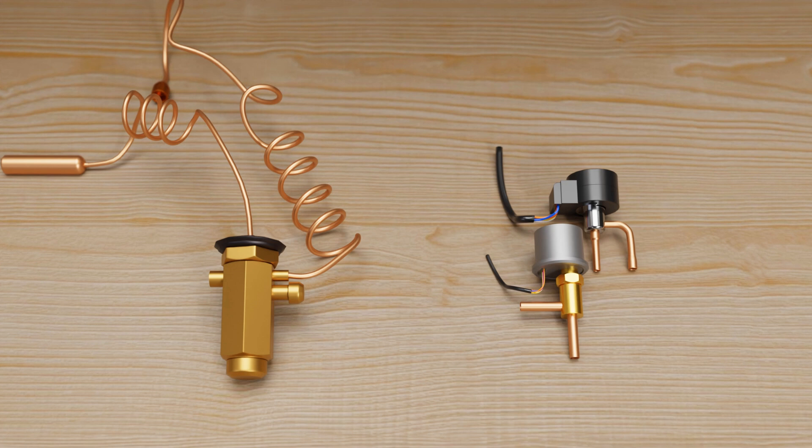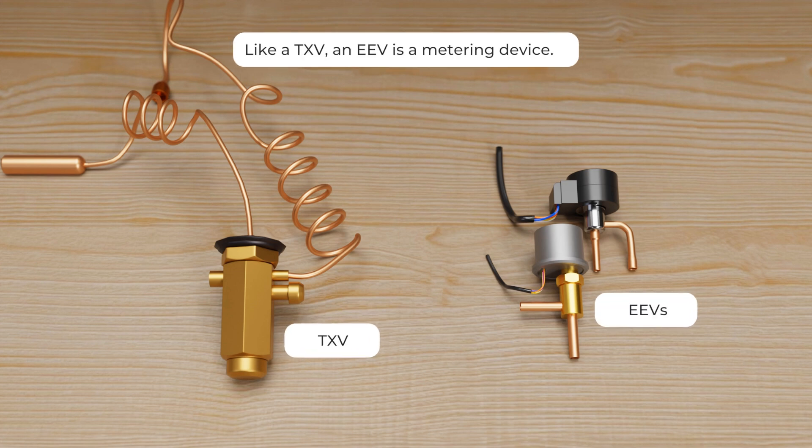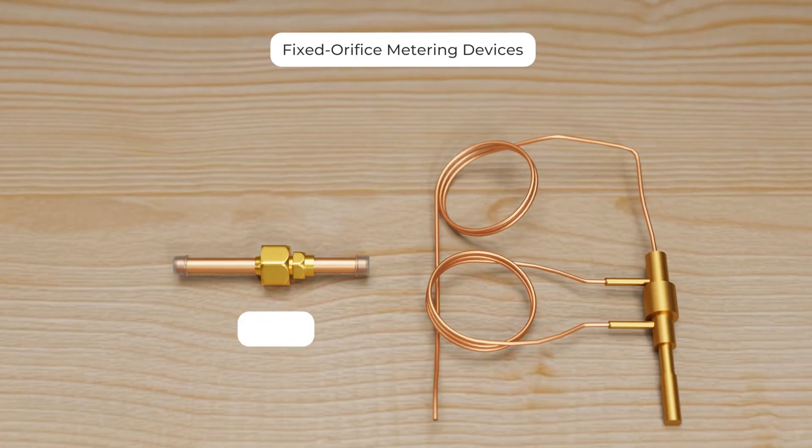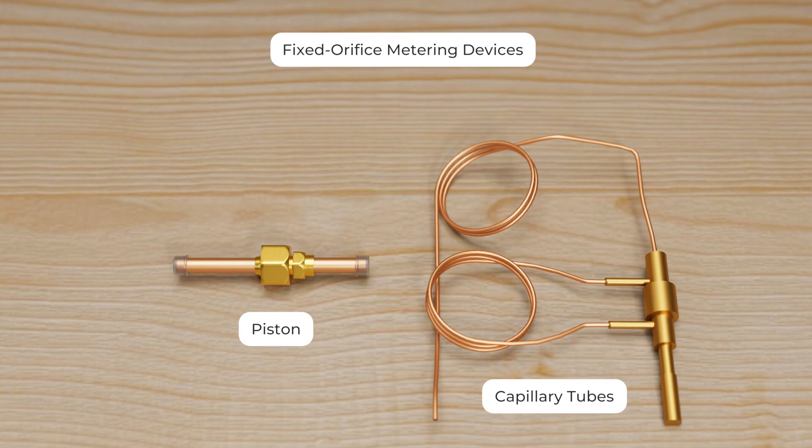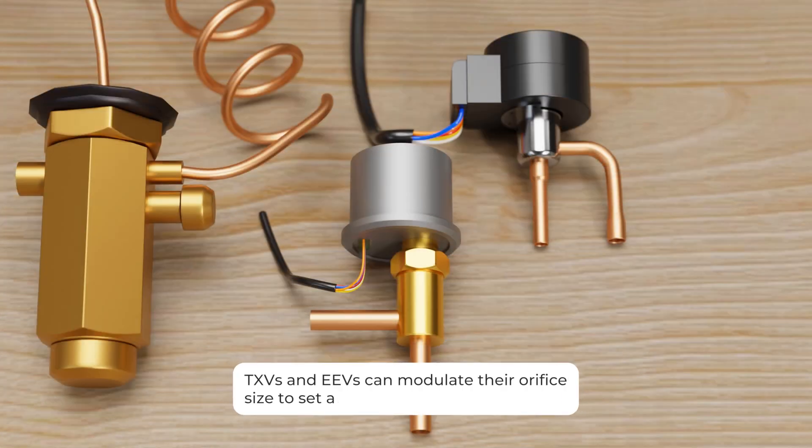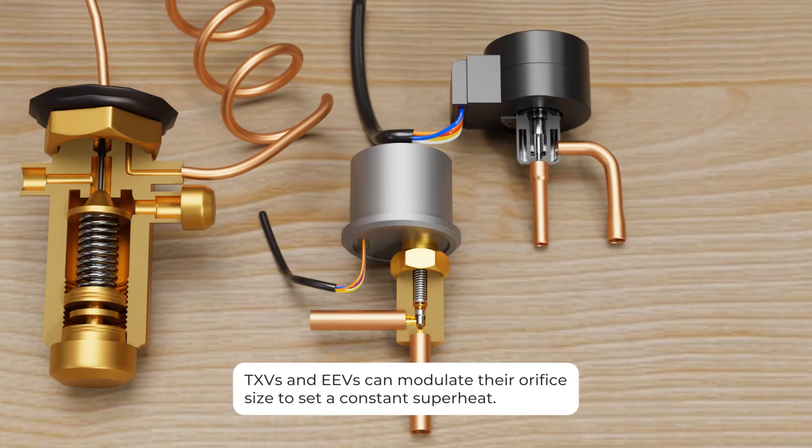Like a thermostatic expansion valve or TXV, an EEV is a metering device. It drops the pressure of liquid refrigerant. Unlike older fixed orifice metering devices, both TXVs and EEVs can modulate their orifice size to set a constant superheat.